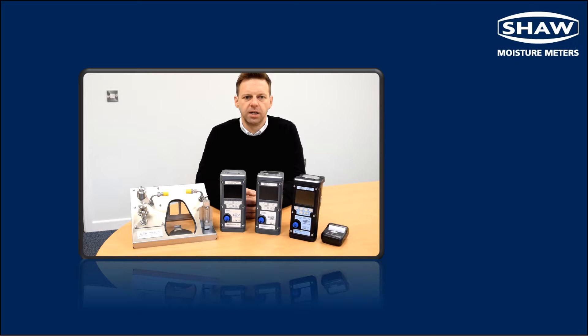The SDH Mini, as with all portable instruments from Shaw Moisture Meters, is designed to be operated at atmospheric pressure. In most applications, any sample for analysis is likely to be at positive pressure.